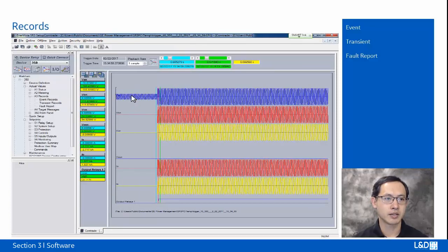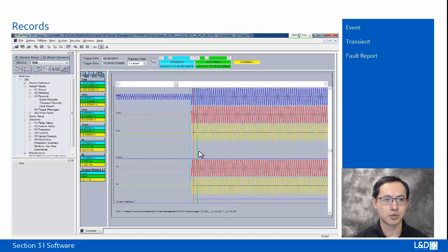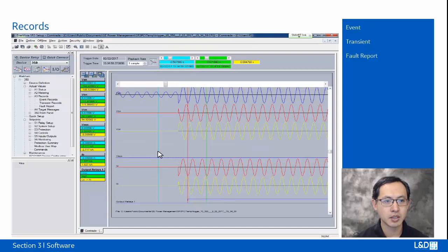So now I started the waveform of the 3-phase voltage and current, and I can drag and zoom in this pre-fault to fault conditions. So for example, I can see the relay operation, output relay. By moving the cursors, I can further zoom in. So we can see that from the pre-fault jump to fault, the time difference is like 1 cycle, 17 milliseconds.